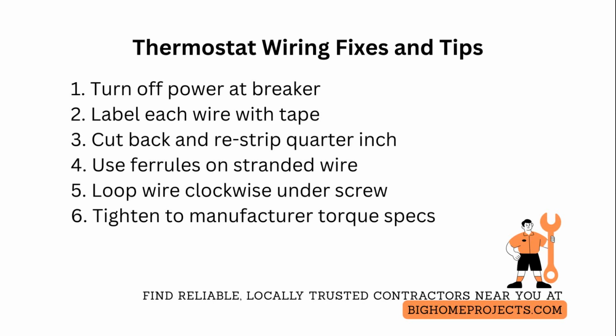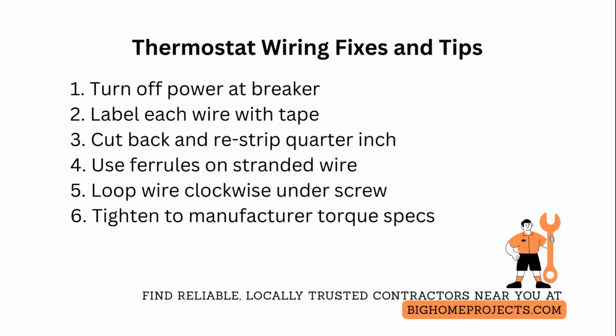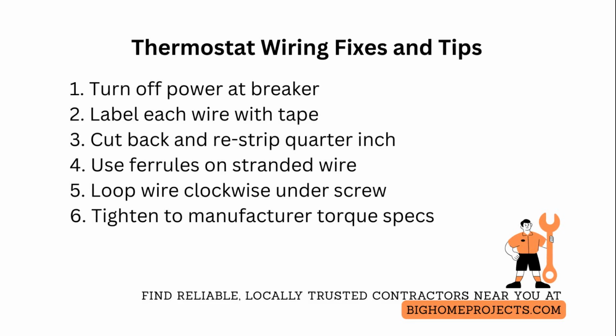Tighten screws to the torque recommended by the thermostat maker, typically snug but not crushing. Too loose equals intermittent contact. Too tight risks breaking thin conductors.